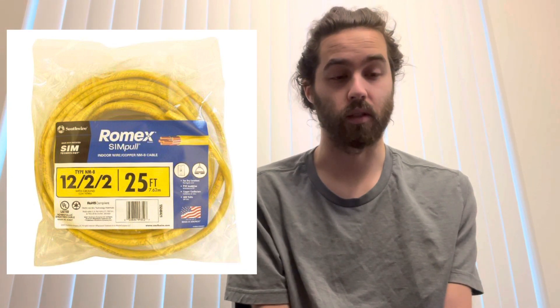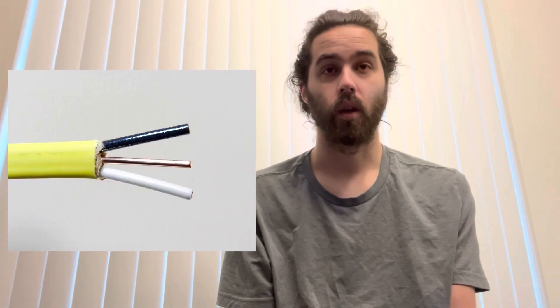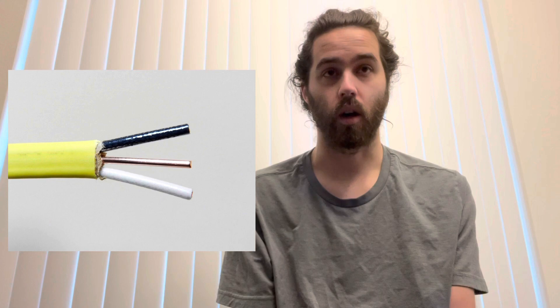The first residential term is Romex, or wire, which is what you're going to be using to wire up houses, even in some commercial applications. It's just a type of wire in a plastic sheathing. You would see it labeled as a 12-2, a 12-3, a 14-2, or a 14-3. Those numbers relate to the gauge of the wire and how many current carrying conductors are in it. A 12-2 is 12-gauge wire with two current carrying conductors — a hot and a neutral — and it doesn't include the ground wire.